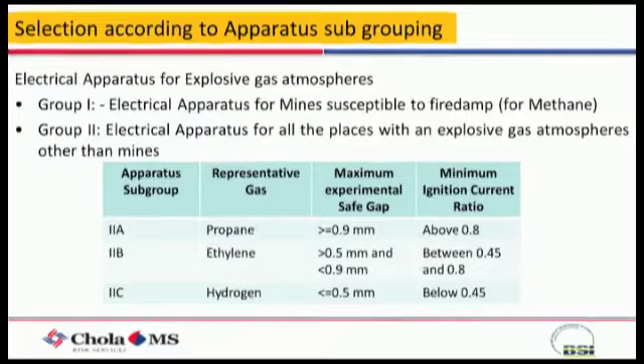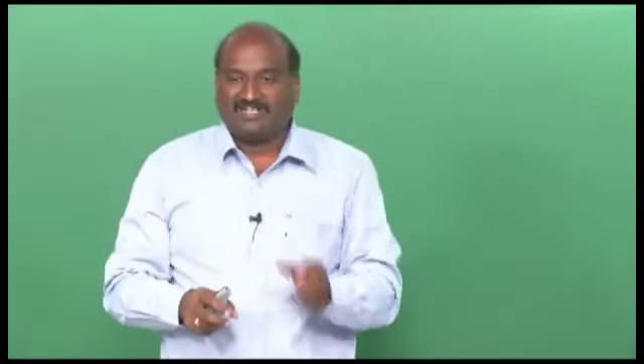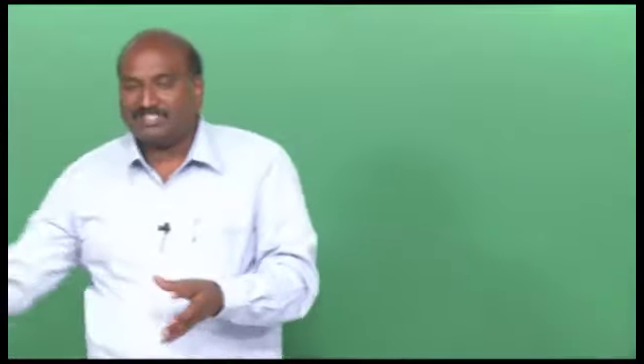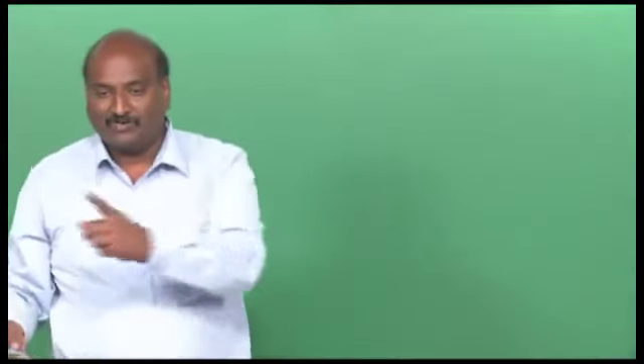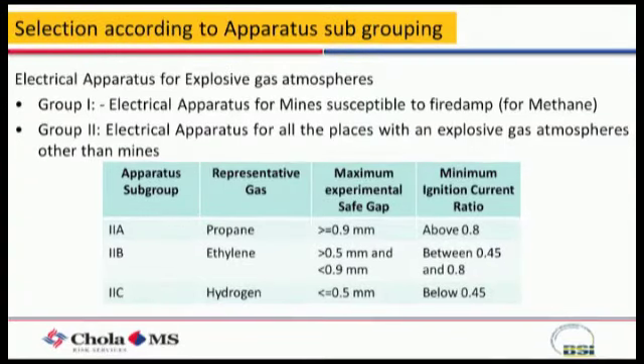Understood why? The previous slide was on temperature, this slide is on gas. Assume in this area you are processing hydrogen, then you first refer to the T column, then the gas group column, and then go to the next level. You need to select all three together, check the nameplate, and then use the right equipment. If you use propane type 2A material in a 2C area, it's again a wrong selection, and it might catch fire.